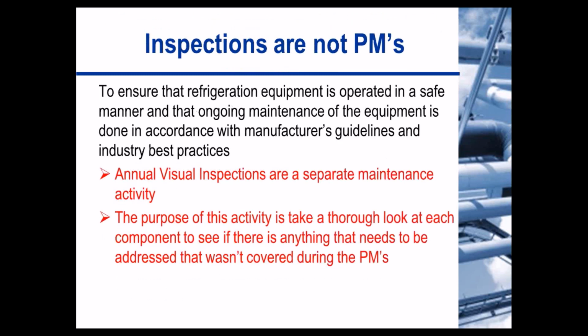So one thing that I want to point out before we get into the inspections is that these inspections are not the same as preventive maintenance. What we're trying to do is ensure that refrigeration equipment is operated in a safe manner and the maintenance is done in accordance with manufacturers' guidelines and industry's best practices. Now, annual visual inspections are a separate maintenance activity. The purpose of this activity is to take a thorough look at each component to see if there's anything that needs to be addressed that wasn't covered during preventive maintenance.